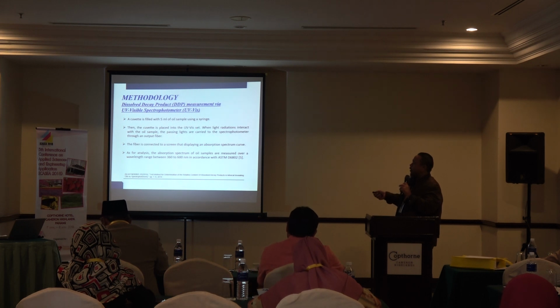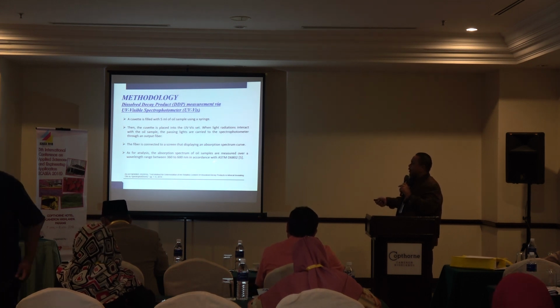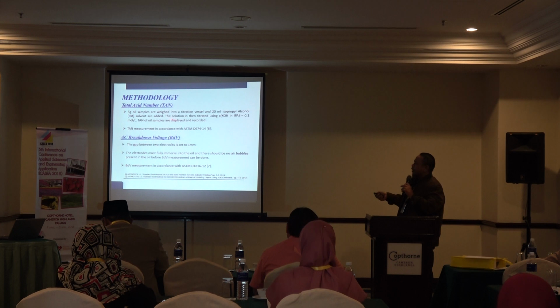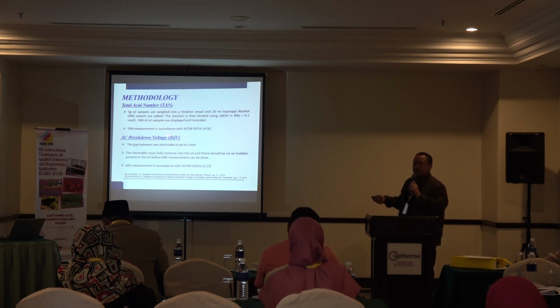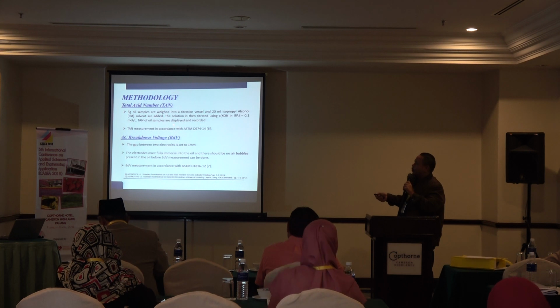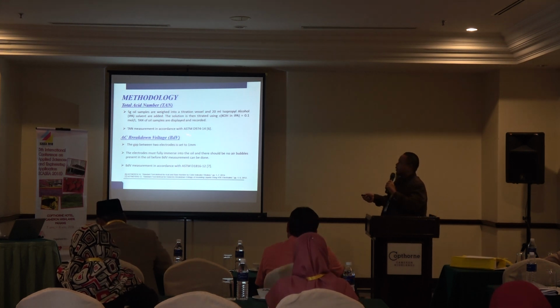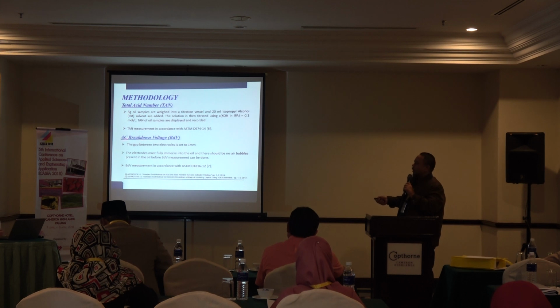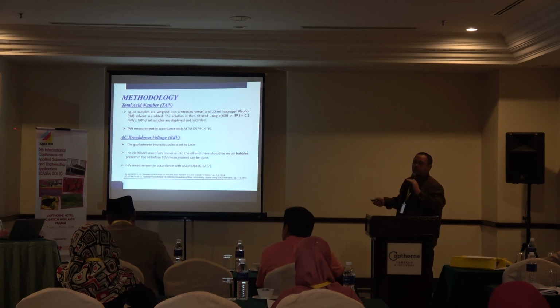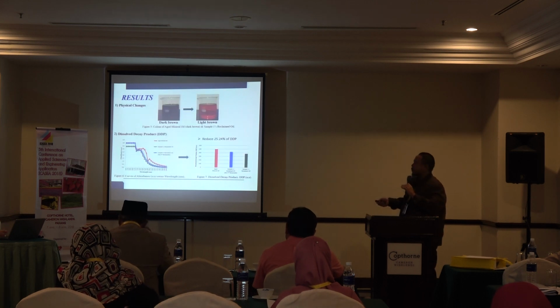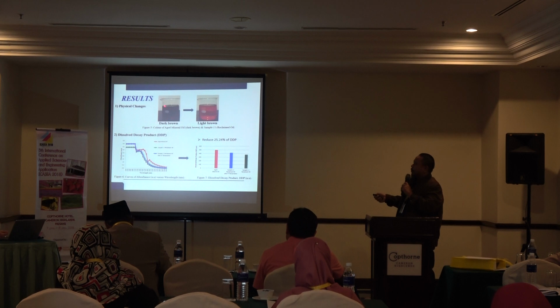I'm using UV-Vis, and we comply with the standard ASTM D6802 to measure the dissolved decay products. Next, we use the total acid number. We measure the acidity of the oil in compliance with the standard ASTM D974. And next, we do the dielectric strength, also called the alternating current breakdown voltage, by applying a high voltage to the oil, increasing it, and seeing the level at which breakdown occurs, complying with ASTM D1816. So we can see that there are physical changes.